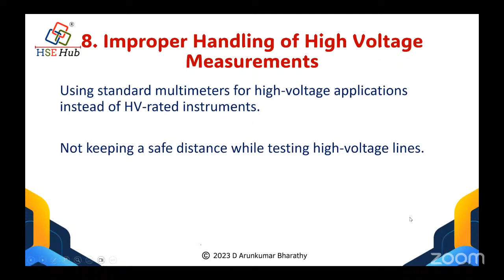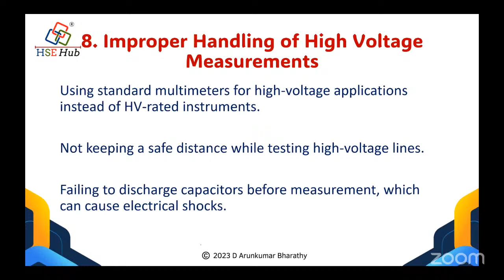Again, not keeping a safe distance while testing a high voltage line is another reason, and so is failing to discharge a capacitor before measurement. This mistake can happen sometimes when somebody is checking batteries. They have to first discharge using the electric discharge rod, then measure. Otherwise, measuring directly without knowing whether it is discharged or not can create a sudden arc, because compared with AC, DC can create more arc. So it can happen in measurement also, right? Hope you are understanding my point.